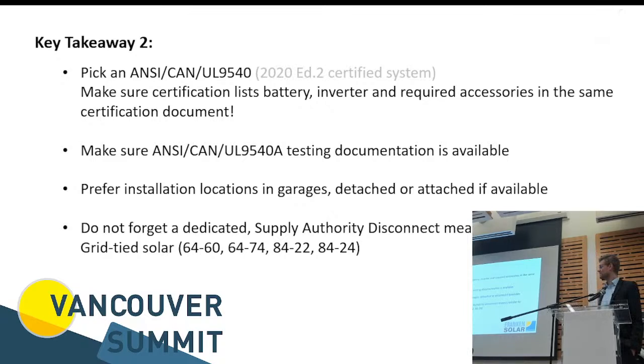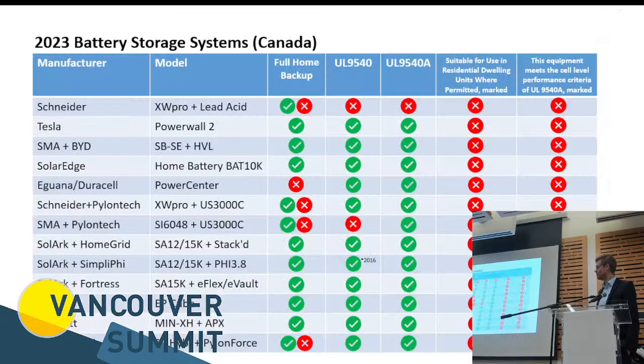And that is in section 6460 and 74, where it's pretty much the exact same as the solar inverter, just another dedicated one for your battery storage inverter. If you do have a hybrid system, then that hybrid disconnect in some jurisdictions can be the same as the solar inverter, because now battery storage and solar is in one unit, having the same disconnect switch. Some jurisdictions also require a battery DC disconnect in addition to the disconnect that comes into, or in most enclosures. So you have pretty much a lot of additional equipment to install under those rules.